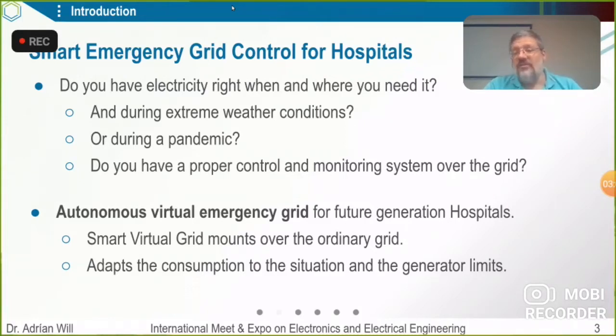So if the outlet is in an operating room, it will provide energy, but if the device is a TV set in the waiting room, it will deny it. The system adapts consumption to the situation and to the generator limit. If the limits of the generator change, for example if one of two generators stops, the whole building will know what to do and adapt itself to the situation.